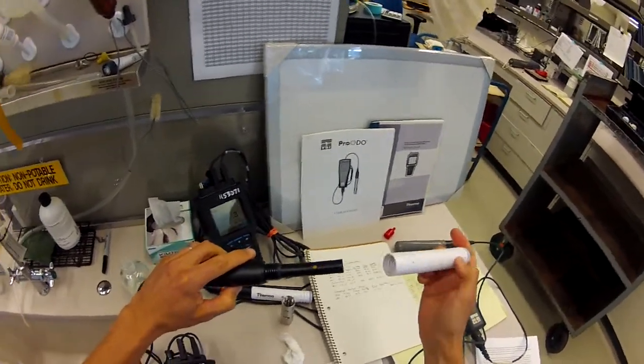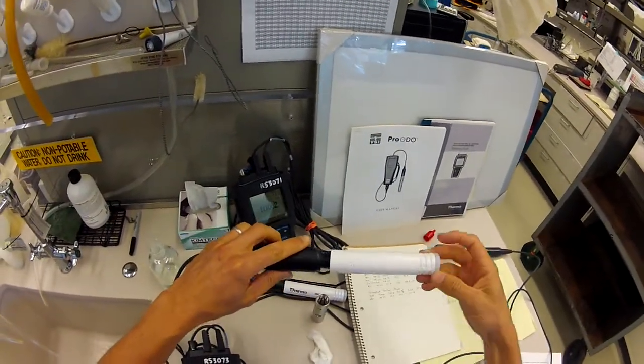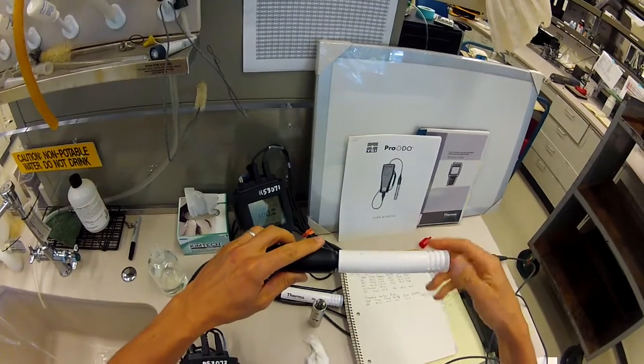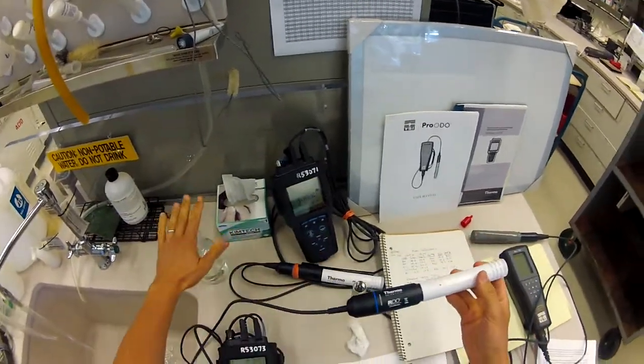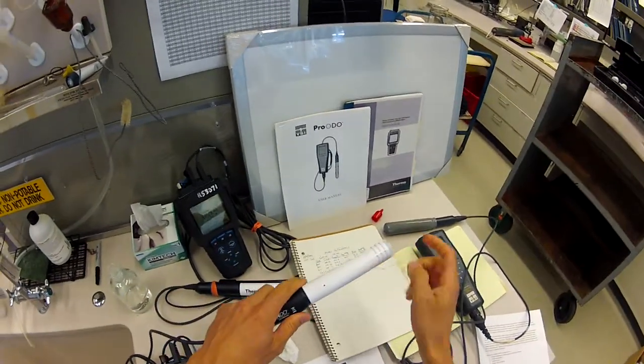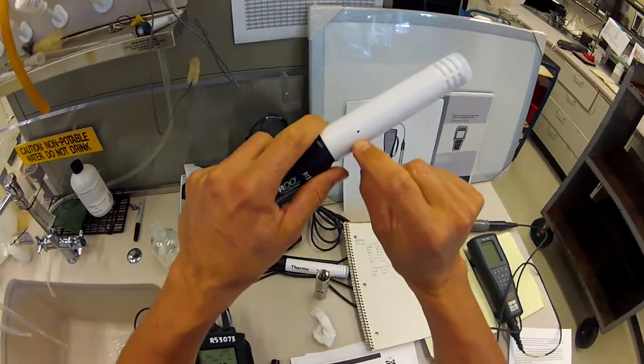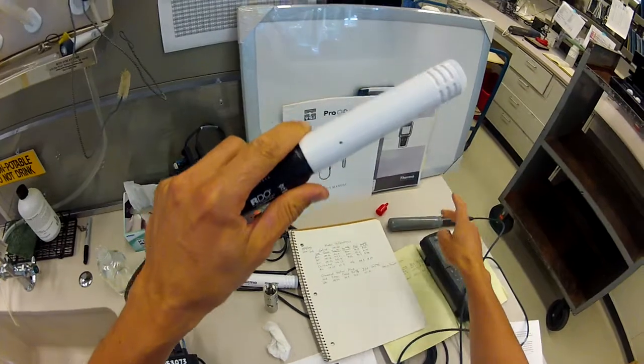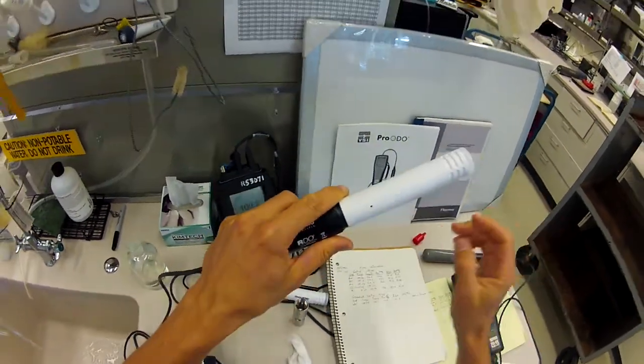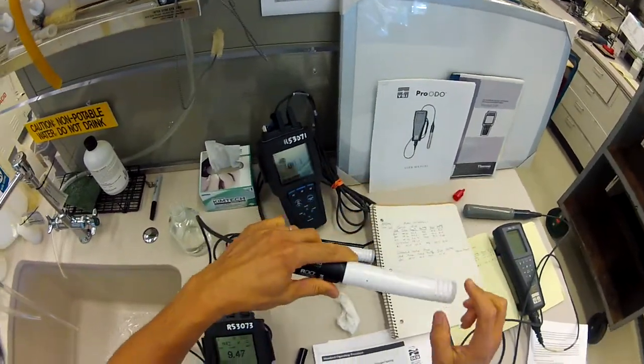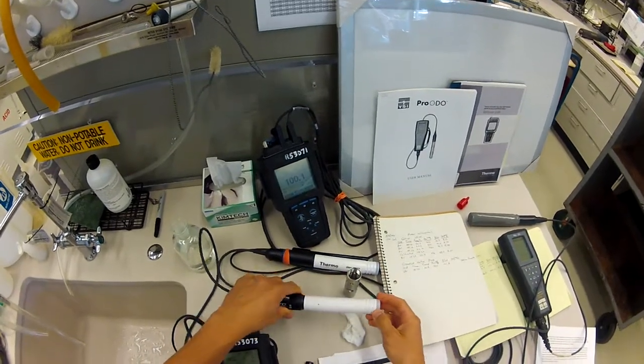So we've got that moist sponge in our chamber and we screw it on. The other element of the calibration chamber, whether you're using something like a BOD bottle or something like this, is that it needs to be vented. Here you can see a vent. The YSI has a vent on the side there as well. All these chambers need to be vented so that they're at equilibrium with barometric pressure.